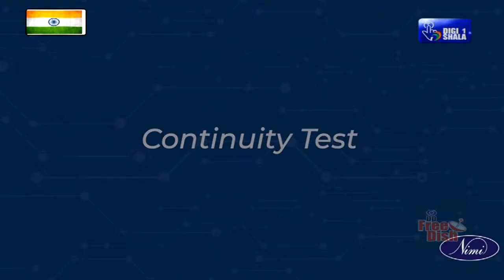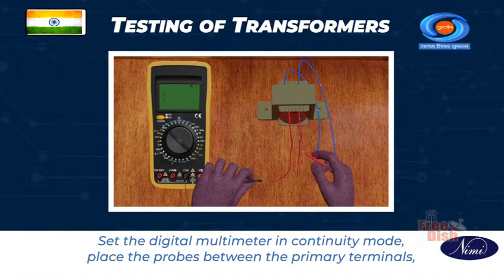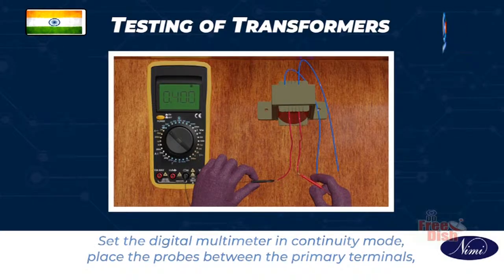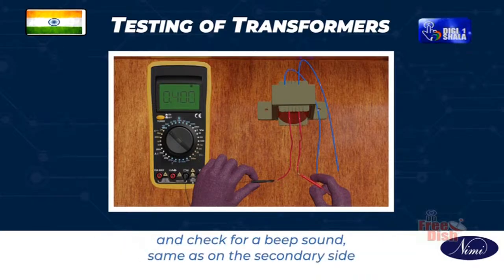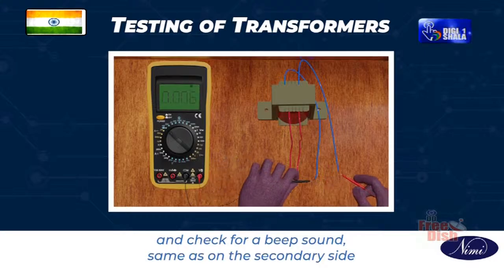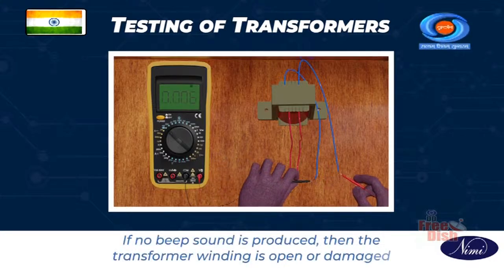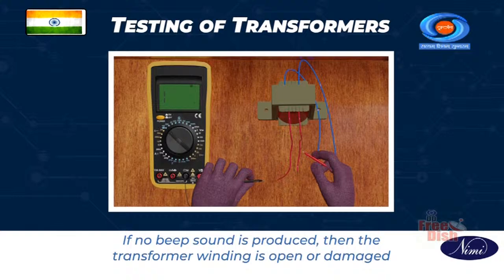Continuity test. Set the digital multimeter in continuity mode. Place the probes between the primary terminals and check for a beep sound, same as on the secondary side. If no beep sound is produced, then the transformer winding is open or damaged.